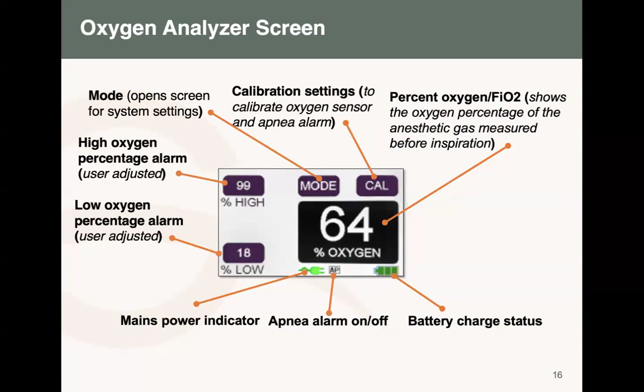And as I said before, calibration is very simple. You go to cal, you go to air, and once it calibrates, you just press go twice, and then it will come back. You just calibrate cal, air, and go. Once it's done, you exit, and then it will be calibrated. So when you have 100% oxygen, yes, you can even calibrate the oxygen.